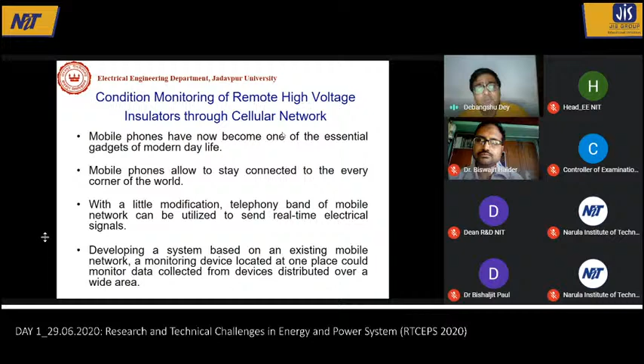So the third topic is the condition monitoring of remote high voltage insulators. You know that there are so many insulators - there may be lots of insulators in our transmission or distribution network. There are so many overhead insulators, and it is very difficult for manual checking of each and every insulator. So what we have planned to do is have a remote monitoring system, so that we do not have to check the insulators manually. We can check them over the mobile network or cellular network.